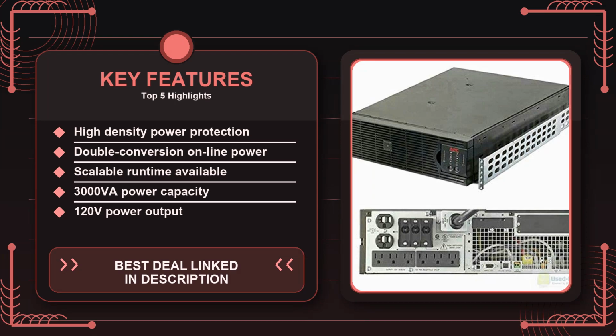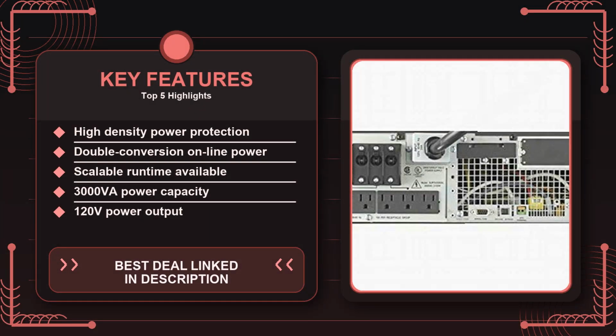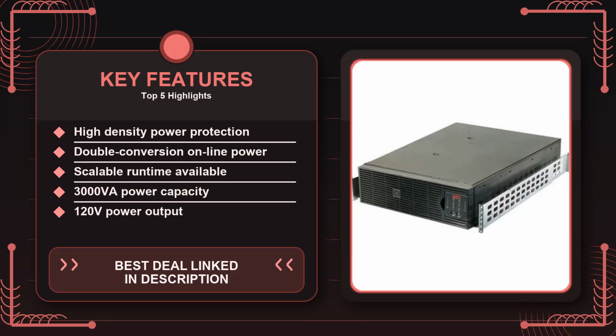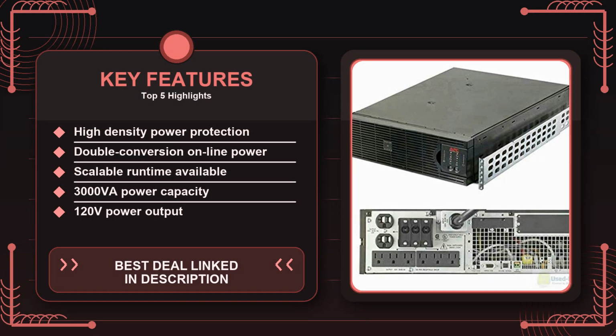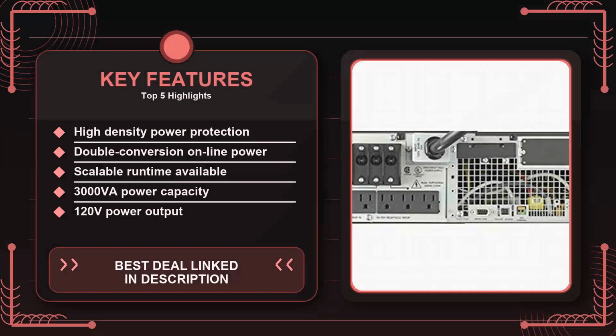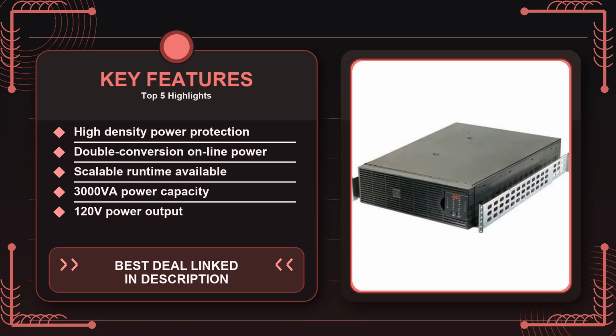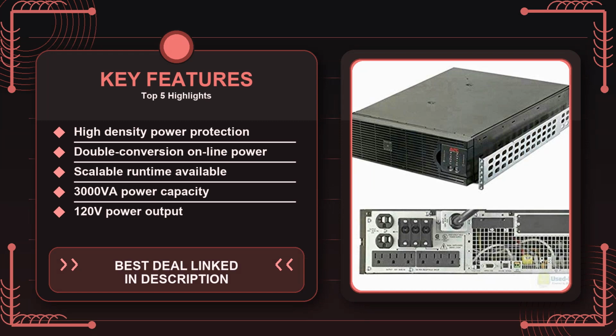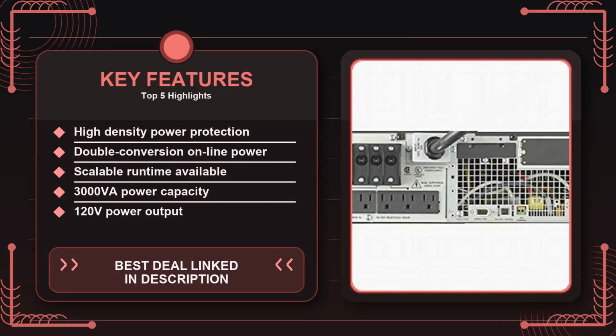If you run a server room with a few rack-mount servers, a couple of network switches, and perhaps an external storage array, you're likely pulling somewhere between 800 and 1500 watts on a regular basis. The 3000VA rating translates to about 2700 watts of continuous output, so you have a decent safety margin. That means you can attach a handful of devices and still have enough headroom for short spikes, which is exactly the kind of scenario where double conversion technology shines. The double conversion design continuously regenerates clean power, so you're protected from sags, surges, and frequency variations, something you'll notice if you've ever seen a network switch hiccup during a brief brownout.